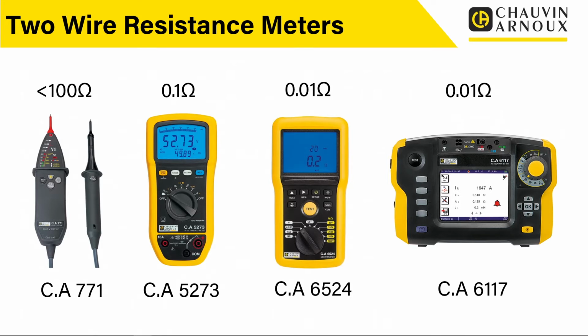So 2-wire resistance testing, it's there. Be aware of the level of accuracy, be aware of the ranges you can get to. And as we said, this is industry standard. Hopefully you can see why we can't just use a normal multimeter to do our 17th edition, 18th edition BS 7671 testing, because we are required to get down to that 0.01 ohms type range. But again, I think we would benefit from going that little step further in those tests, and that's something that maybe we can discuss a bit more later on in the live Q&A.